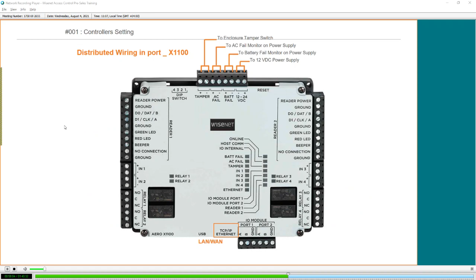Okay. Now, if you're going to use the Wiegand method, in that case, you would probably have first a master controller. Do not worry about the models, just a master controller, which is the first controller. After that, there is an RS485 connection, which will go to the subcontroller. The subcontroller is the one speaking to the reader. The subcontroller will also control the lock and push button. When you use a push button, it means you are controlling only one door. You swipe your card, and then when you leave, you press a push button. So if the board has two readers, each can be used for one particular door. So a total of two doors can be controlled from one controller in that case.